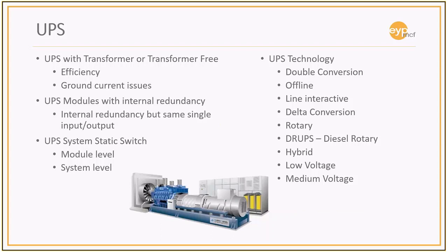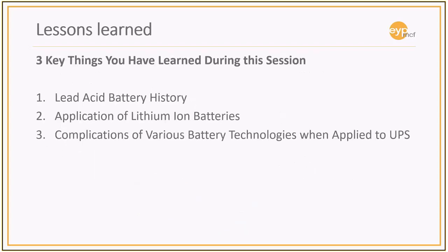And then there's a whole line of UPS systems that don't really use batteries. Rotary systems can use flywheel type technology to carry you over until your generator starts, or they have actual rotary batteries, flywheel based systems that can carry you for 5, 10, 15, 20 seconds until your generator starts. All these different technologies are interchangeable depending on how much space you have and how much money you have, because these systems will vary in cost and application over time.